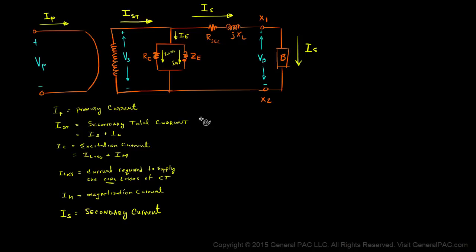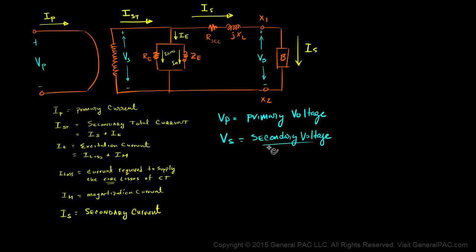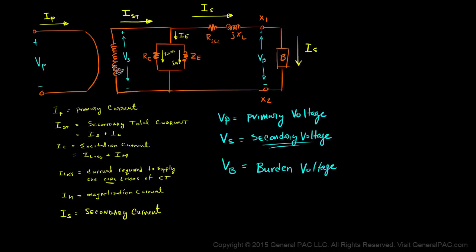Now let's move on to our voltages. VP is our primary voltage. VS is our secondary voltage — the secondary voltage is described as the voltage across the magnetization branch, which is a very important voltage. VB is our voltage across the burden, which is also very important. Often times VS and VB are used interchangeably, but they should not be — they are two different voltages.